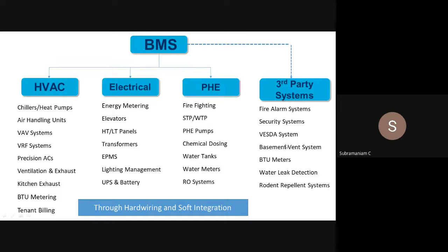What is called third-party is where the intelligence is already built into those systems. The fire alarm system, the detectors are there, everything is there. In the basement ventilation system, the PLC is there. The programmable logic controller is there. It will regulate all the jet fans. BMS will not interfere with that control logic, but it will bring in all the data. And if you want to link that data to switch off some AHU, switch on some AHU, or do some other function, it can all be done at the system level, at the higher level. So that is what the BMS does.